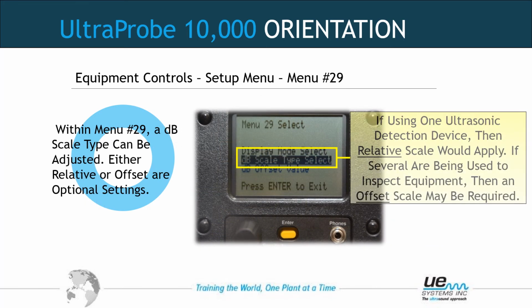dB scale type select. This is fairly important if being used in conjunction with the Ultraprobe 401 grease caddy. The readings may have been taken and trended with the Ultraprobe 10,000 and a stethoscope module. The Ultraprobe 401 grease caddy has a magnetic mount or a magnetic transducer. Those different modules will read different decibels. So you can either offset the scale on the 401 grease caddy or offset the scale on the 10,000. Typically, inspectors choose to offset the 401, not the 10,000.